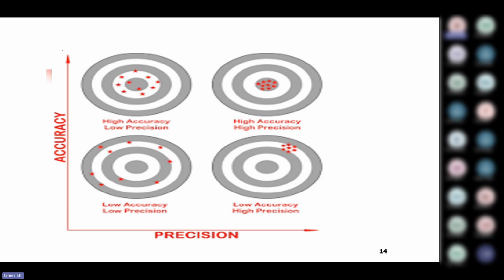Even if you are achieving this ideal configuration today, the reagent you are using and the calibration can change it. Sometimes some people don't even stock calibrators according to the manufacturer's specification. Most calibrators are valid for 28 days when refrigerated. If you must ensure that they keep longer, up to 90 days, then you need to aliquot and freeze them. But I see laboratories where somebody will say, I forgot. And in the second month, they are still using it to recalibrate. You're not going to get an effective calibration of your system. You're going to be having cases of inaccuracy. Your accuracies will be low, like what you have in the lower quadrants.